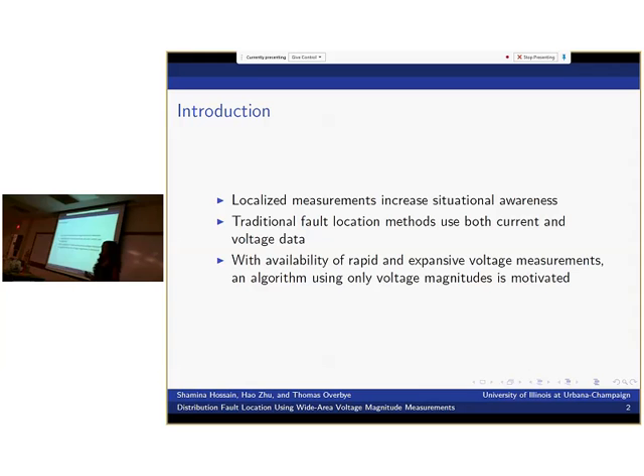And so first, a little background. With the Smart Grid initiative underway, there's a big push for increased situational awareness. As a result, there are many devices and systems that can take fast sampled, localized measurements in near real time, such as voltage magnitudes. Traditionally, for fault location algorithms, both current and voltage measurements were used, and these measurements are often made at the substation end of the feeder lines. But now with these localized measurements, we can get voltage magnitude measurements from anywhere on the line, which motivates an algorithm that only uses those voltage magnitudes, reducing the amount of data that we need to process because we're ignoring current entirely.